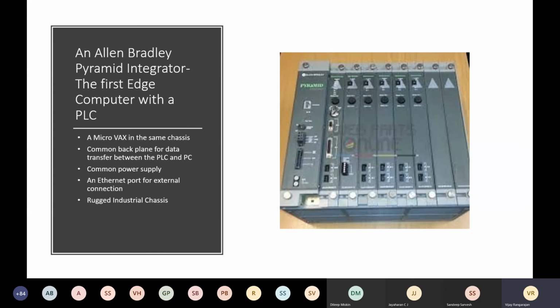To keep it simple, I'm making it 3 systems, and this had to be coordinated precisely because the robot is moving at 4 feet per second. So in half a second the robot has moved 2 feet; in 250 milliseconds, it has moved 12 inches, 1 foot. The scan time of the PLC, because of the enormous amount of programming and data processing it was performing, was over 250 milliseconds.